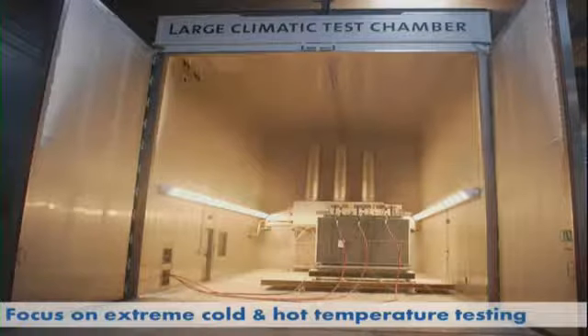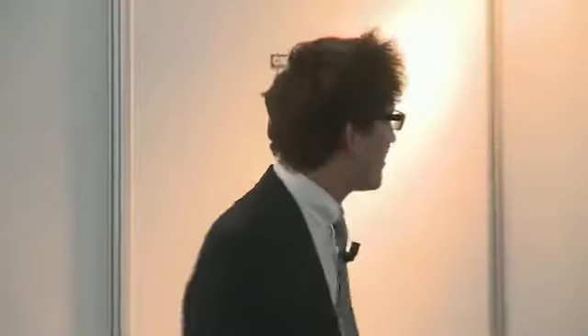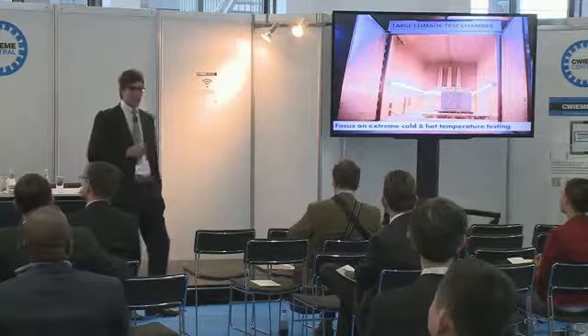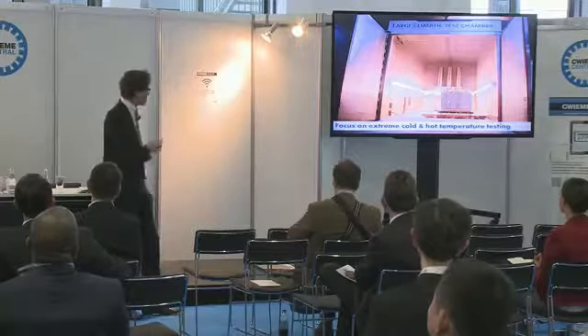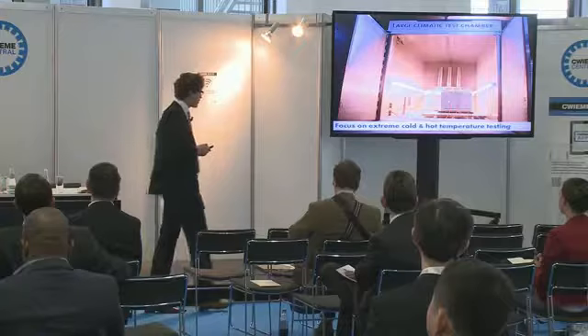One investment I'll talk about is one of the largest climate chambers in Europe, focused mainly on extreme cold and hot temperature testing, for validation tests on transformers. The unique thing about this facility is that we can handle more than 150 ton heavy machinery inside, with a foundation of 40 ton per square meter. We can cool heavy machinery down to minus 60 degrees, and in the hot range we can test at plus 60 degrees. It's quite large - here you see a 5.5 MVA transformer, not a really big one, but we can handle larger ones too.